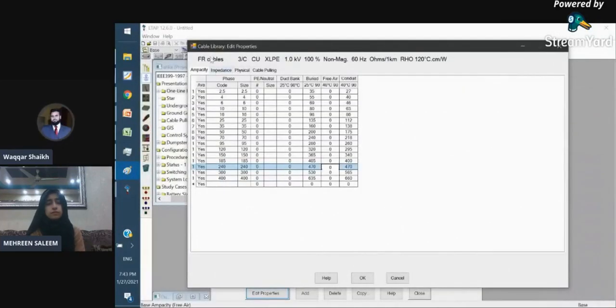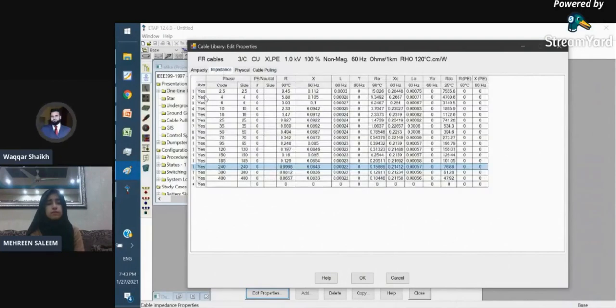Go back into the same window and you have the impedance tab. Here you can find, for different sizes of cables under the FR cables manufacturer, the values given, 90 degree resistance, and many other values like zero sequence. For normal AC distribution studies and network studies, we are not concerned about the zero sequence. We just focus on the positive sequence impedances, which are the impedances given in the cable manufacturer's database. For example, for this 4 mm square cable, the existing resistance is 5.88 ohms per kilometer, and you also have reactance in ohms per kilometer. So you are just overriding these values based on the manufacturer data for however many types of cables you have, like a 4 mm square cable in your project or a 6 mm square.